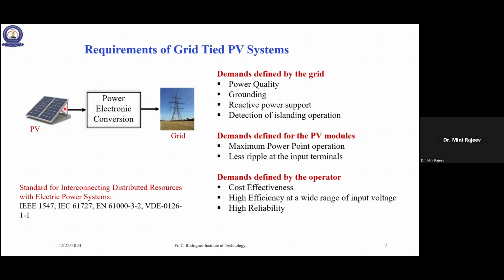Now, you know that there is PV that generates DC and grid is AC. So we need some conversion, power electronic conversion in between. The DC should be converted to AC. There are some demands defined by the grid, by the PV modules, and by the operator. Demands defined by the grid include power quality, which includes voltage sags, voltage swells; all that time you should maintain the power quality. And then grounding issues. You should also take care of the safety part of it.